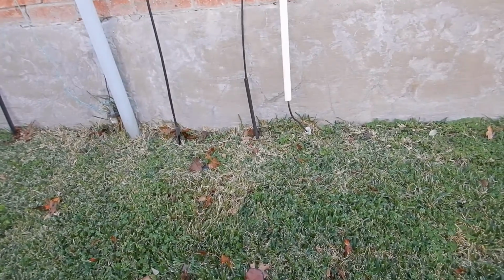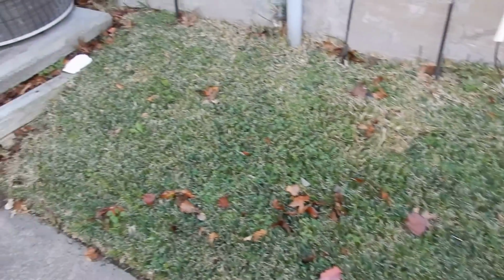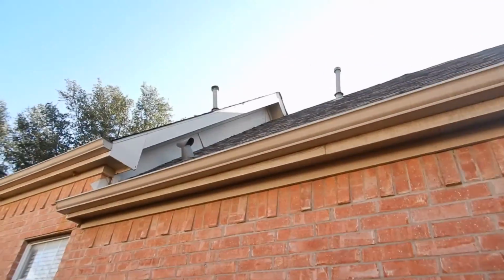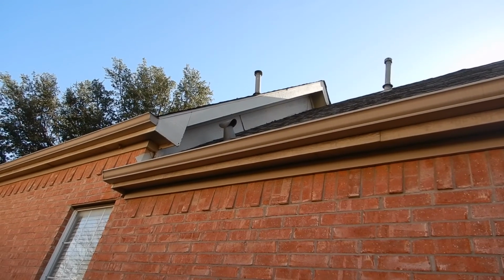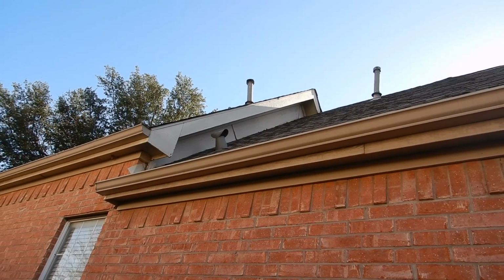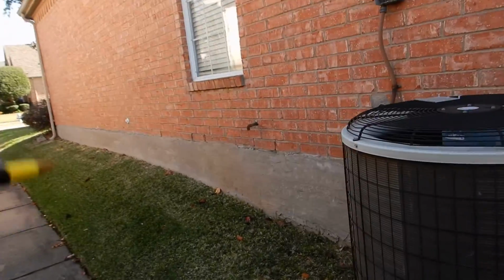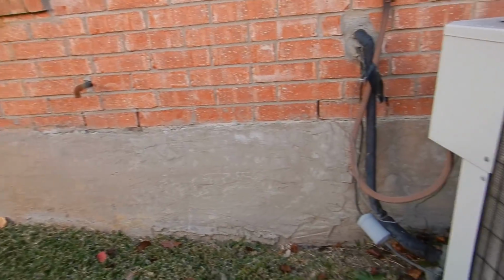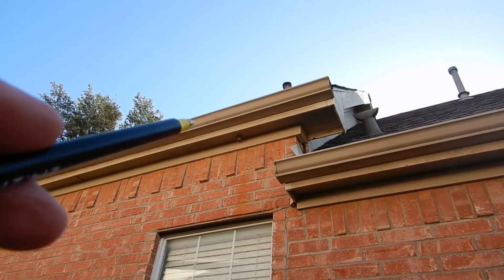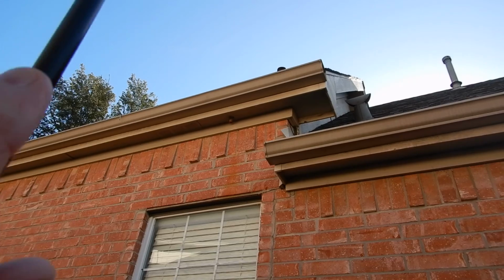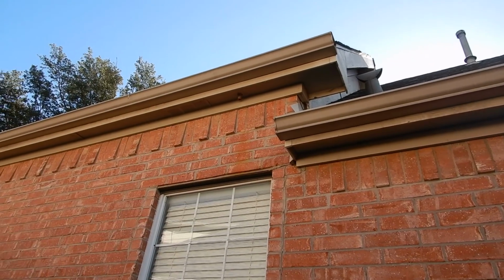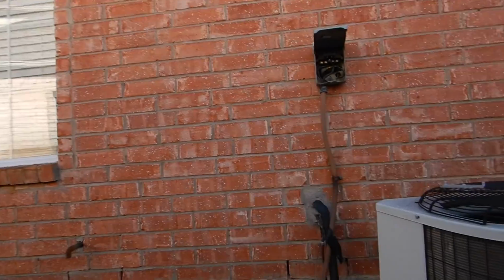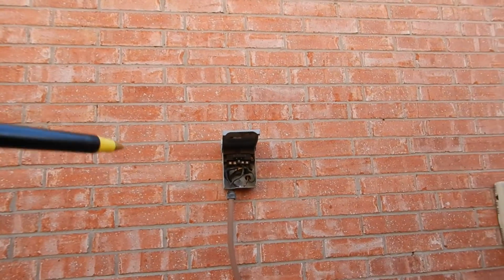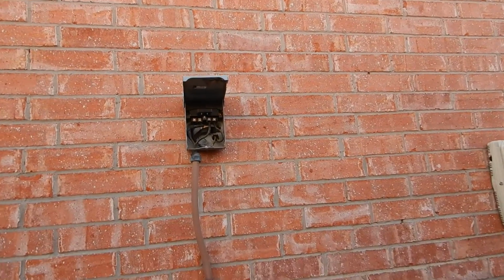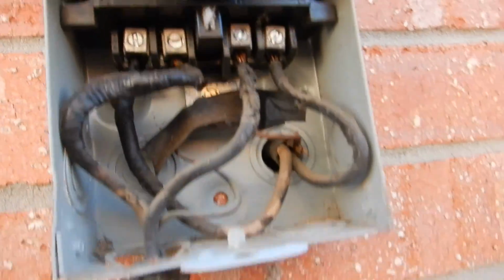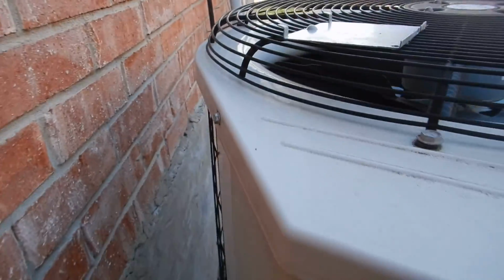So what did we learn? We learned our control conduit for the sprinkler system is broken. We learned that our clothes dryer vent does not have a backdraft on it. We learned that our water heater discharges too high from the ground. We also learned that our evaporator coil has got some rust around it. It's in a good place. You can see the rust right there on the brick where it's happened a little bit. We learned that our disconnect should have been sealed. We learned that some of our disconnect cables have been overheating. We learned that our conduit to the disconnect is loose. We learned that our coils are dirty.